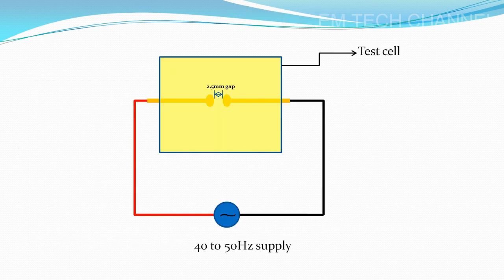And this is a schematic of how the test cell would be. You can see this is the test cell, and in this the bronze or copper or stainless steel polished electrodes will be there, and a 2.5 mm gap will be available between them, and the oil is filled in this, and the 40 Hz to 50 Hz supply frequency is given, and the voltage will be increased at a rate of 2 kV per second till the breakdown occurs or till the recommended breakdown voltage level is reached. And now let's see how this breakdown voltage test is carried out inside.